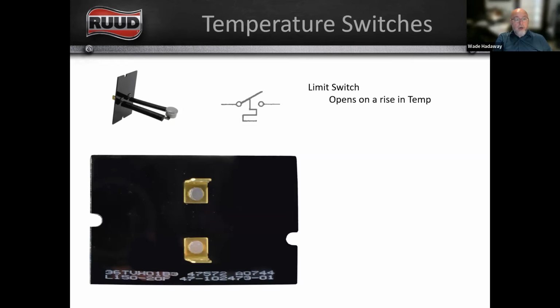Limit switch is the same way, right? That squiggly line tells you that it's temperature, whether it can push up to open on a rise in temp or pull down to open on a drop in temperature. You're going to be able to just see that from looking at the diagram. This is a limit switch for a gas furnace.